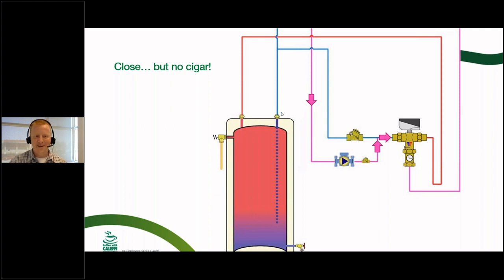But you know what? Sometimes you just got to do what you got to do. It's not always the most ideal situation, but another way that was going to work is the fact that they were actually able to completely gut out that swing check that was in there. So they opened it up, they gutted out the swing check. Somebody got out their magic marker and wrote, you know, removed check valve from the swing check, and now what they have the ability to do is go backwards during times of no demand, backwards to that cold inlet of the mixing valve, down in through the tank, and then back up through the tank to go all the way back to that hot inlet. So now they're not going to run into recirc creep anymore, or recirc droop anymore, because the mixing valve is going to be able to add heat to that loop, again, by going backwards through that tank and all the way back around again. So it was a bit of a maze, but it was an easy little fix.